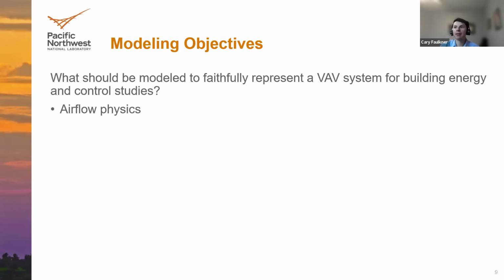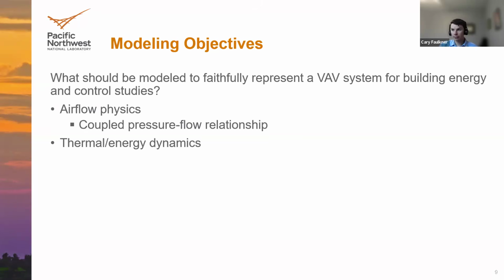I think probably the most important thing is going to be the airflow physics, right? That's the key part of these airside VAV systems. And one aspect of this I mentioned is the coupled pressure-flow relationship. As I mentioned with the fan control and the dampers, there's this pressure aspect that's going to control the fan and inform what's happening at the zones, and that's going to be tightly coupled with the airflow. And so being able to model that relationship is perhaps critical.